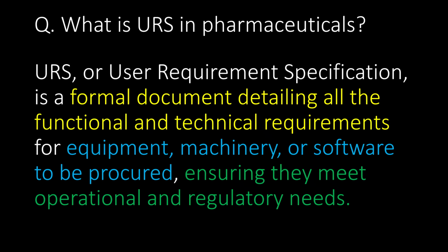What is URS in pharmaceuticals? URS or user requirement specification is a formal document detailing all the functional and technical requirements for equipment, machinery, or software to be procured, ensuring they meet operational and regulatory needs.